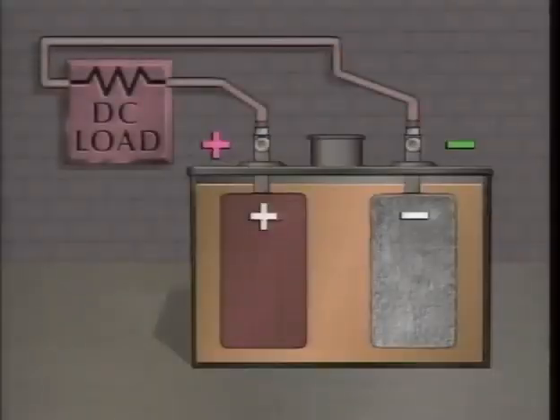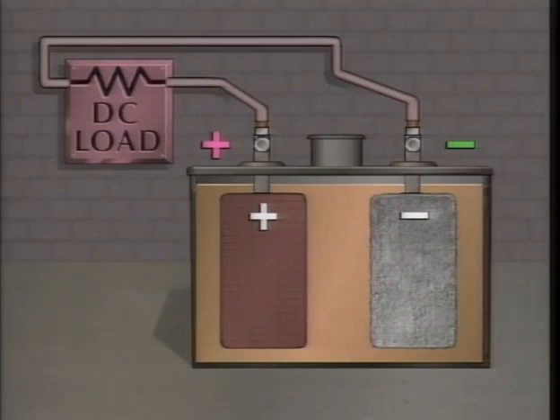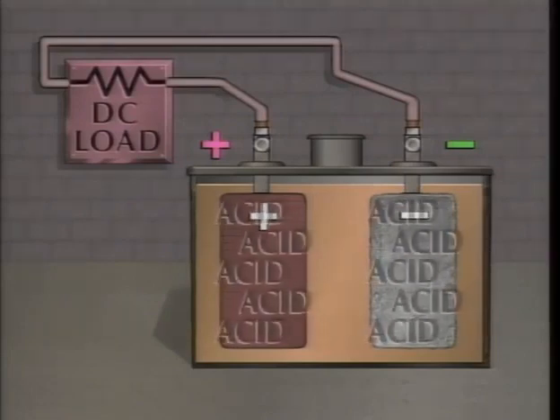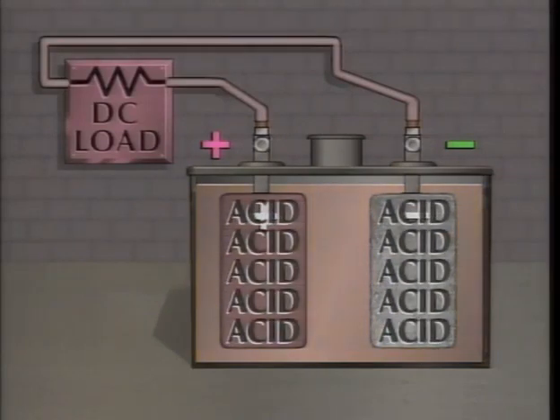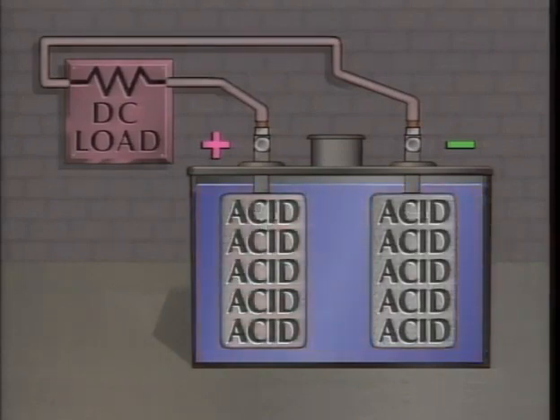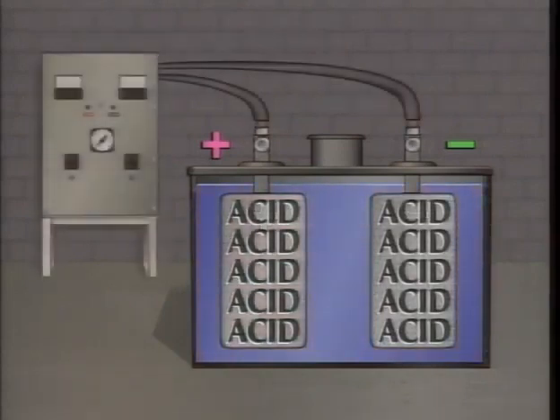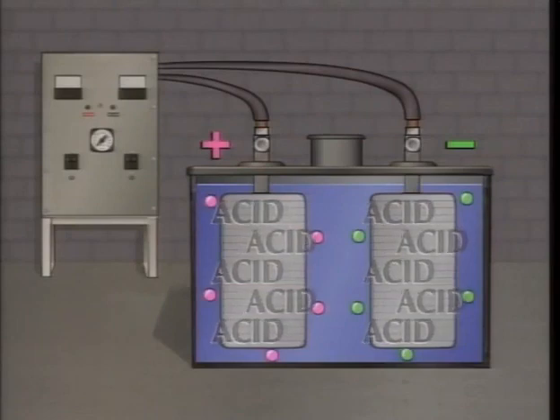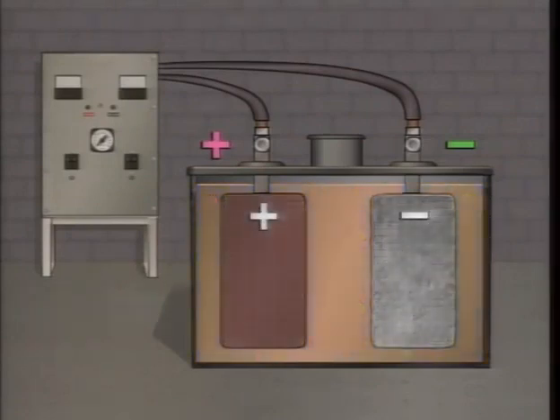You may also know that as a cell discharges, the specific gravity of the electrolyte decreases because sulfuric acid leaves the electrolyte and combines with the lead in the plates. As the cell is recharged, the specific gravity increases because the sulfuric acid is driven off the plates and back into the electrolyte.